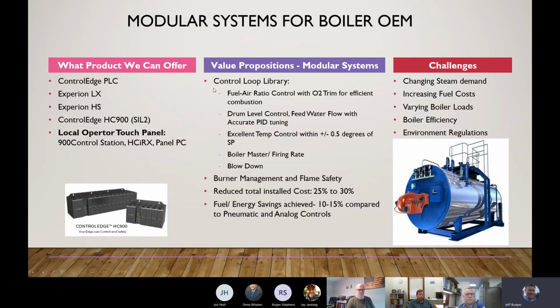The modular system, as we move over to the right-hand side, we're talking about out-of-the-box functionality with the control scheme within the HC900. There's a library that you can build for fuel air ratio control and O2 trim. So on some of the smaller package boilers, Honeywell used to have the ControLinks or another PLC that might do the fuel air ratio.